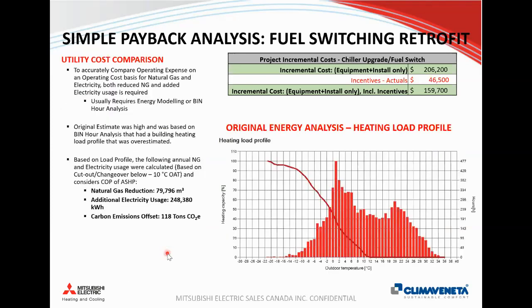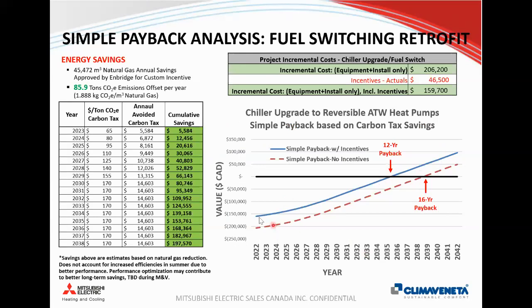So you might also be thinking, what about the operating cost, because you have to buy electricity? So originally, when we were working on this project, we actually provided an estimate taking into account our similar bin hour analysis with a load profile from the building, which is taking into account the heat pump's efficiency at different points and comparing that to a boiler. It's important to have an accurate load profile, because if the load profile is overestimated, then the savings will be overestimated. So for the previous example, where I'm just showing it on the carbon tax, I didn't compare these same ratings of 86 tons because I need to know how much electricity has been added.